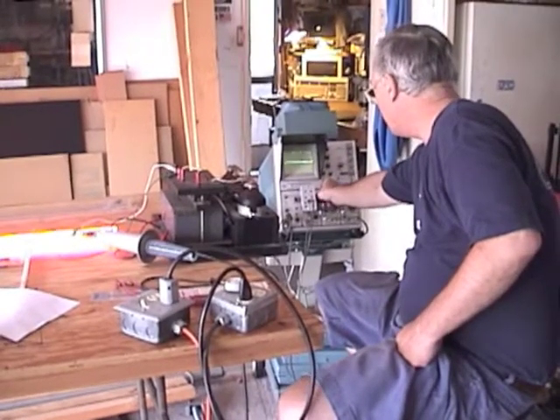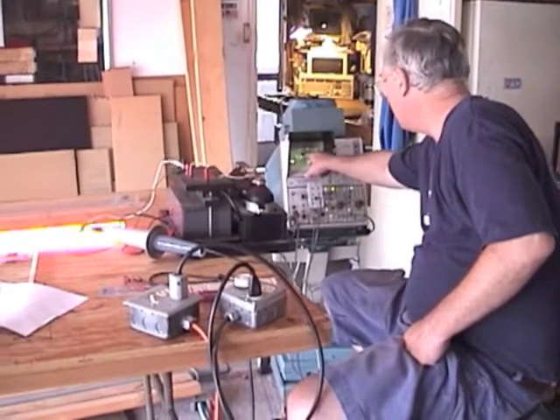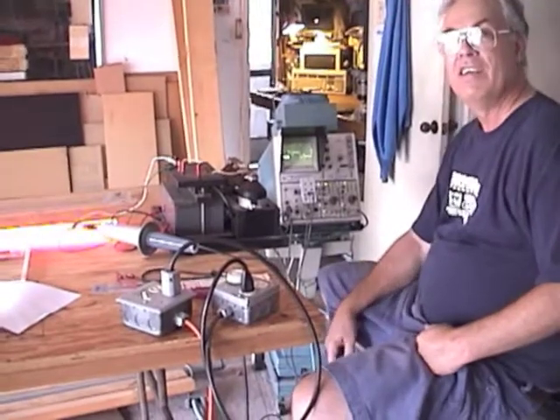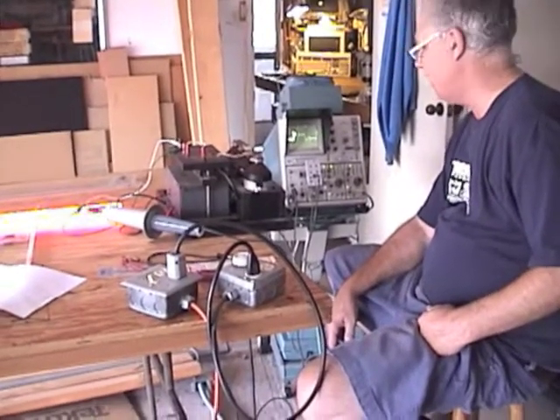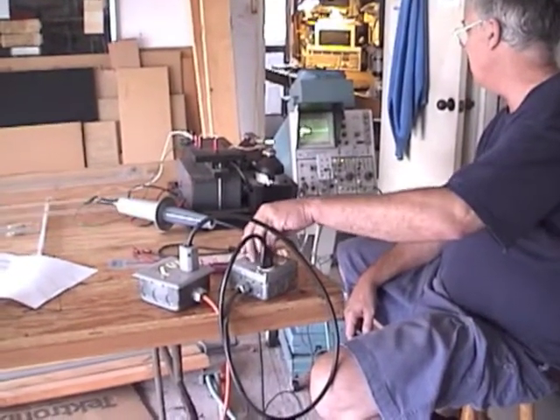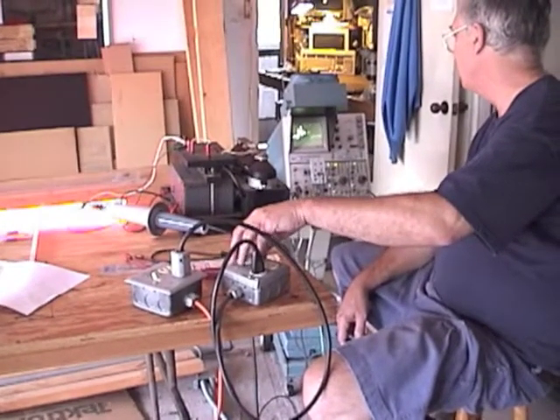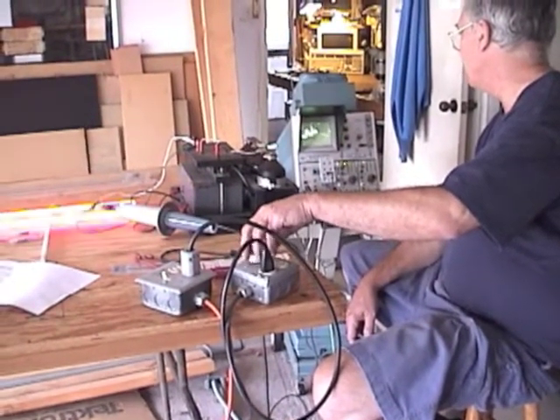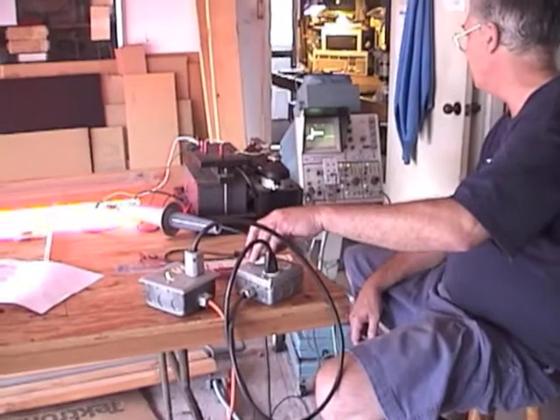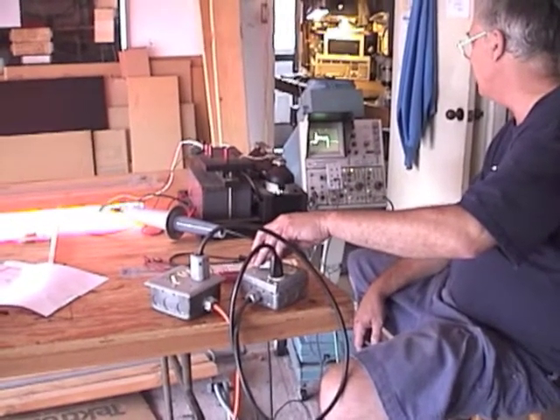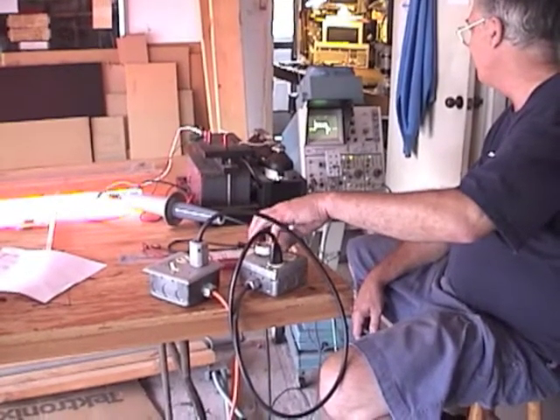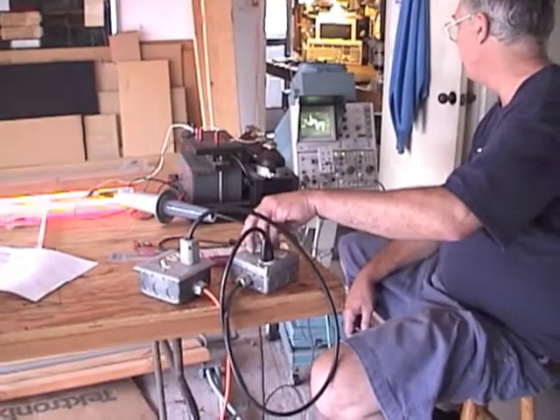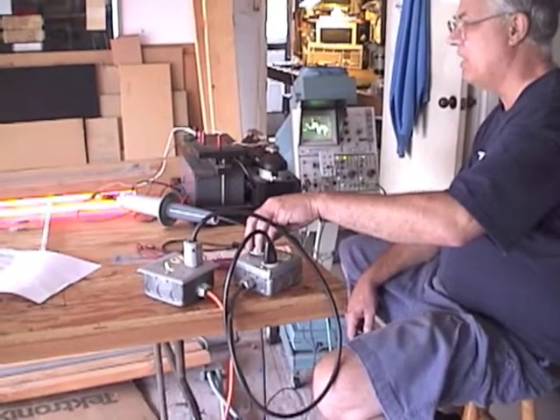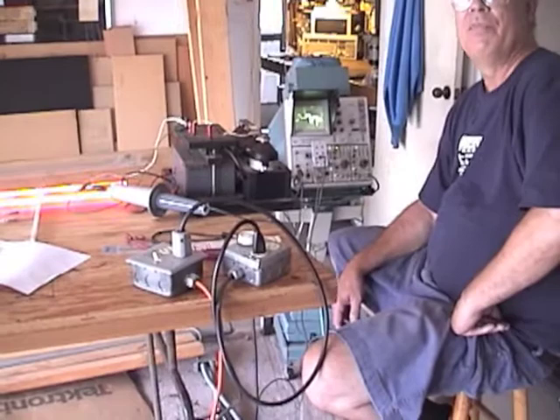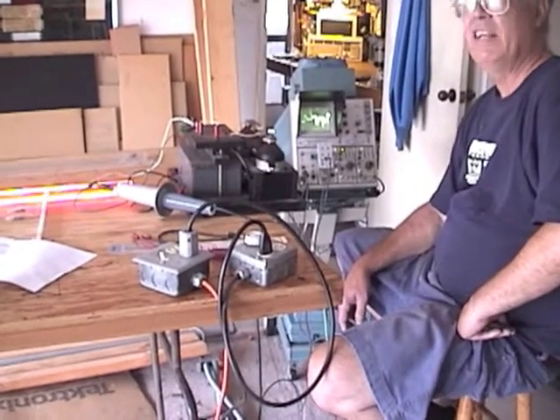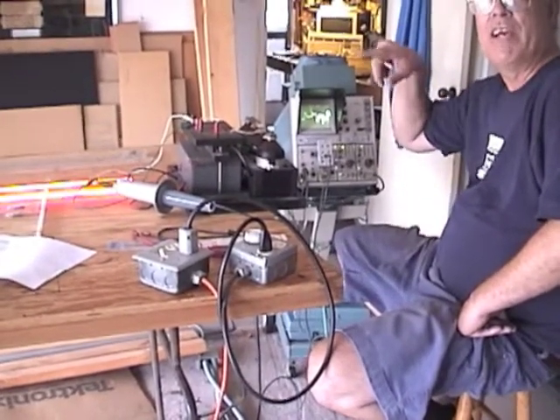Let's see, where are we? 2, 4, 6 kV. So I got a 6 kV voltage spike there on ignition. The size of that spike varies as a function of how much dimming you've got. When it's lit all the way, it's only about a 5 kV spike. So running a partially lit red sign on a dimmer is actually slightly harder on the tranny, voltage spike wise.